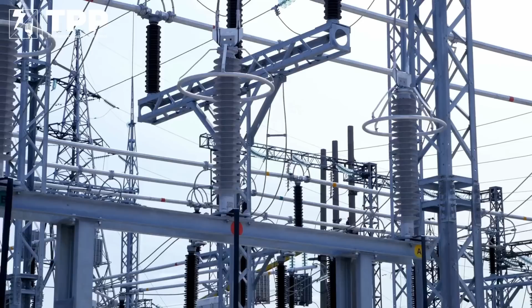With the higher voltage, we need to have the highest physical spacing between the conductors because air is an insulator. Correct. So its footprint is much larger than the medium voltage or the low voltage. Same applies with the current. So based on the fault current study, those could be different for high voltage, medium voltage, and low voltages.